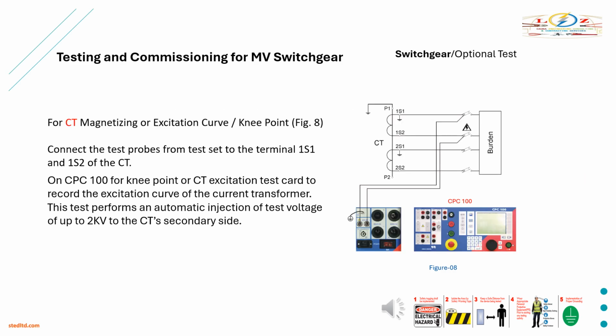For CT magnetizing curve, knee point, as shown in Figure number 8. Connect the test probes from CPC 100 to the terminals 1S1 and 1S2 of the CT. On CPC 100, use the knee point or CT excitation test card to record the excitation curve of the current transformer. This test performs an automatic injection of test voltage of up to 2 kV to the CT's secondary side and test results are automatically generated.